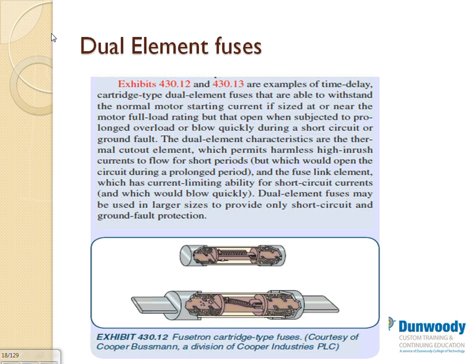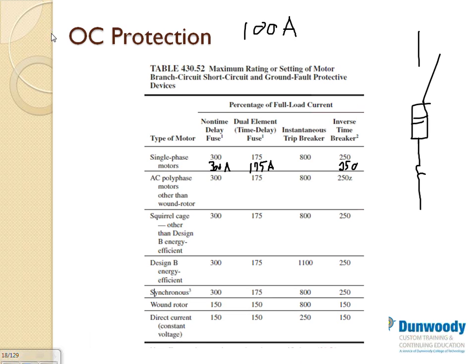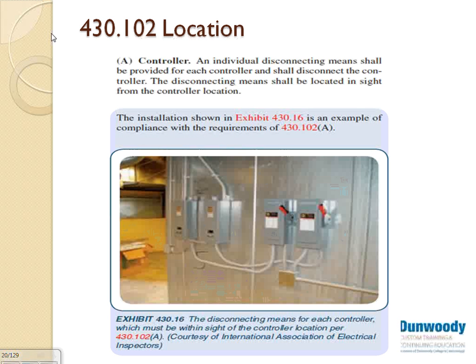So if we have a dual element time delay fuse, you have two elements. One element will look at the overload, and the other element will look at the short circuit. If you have a huge amount of current going through the fuse, it will trip fast. If you have a small amount of current higher than the rated amps, it waits, it could be a minute or two or three, and then it trips. That's an overload condition. So that's the two elements in a time delay fuse.